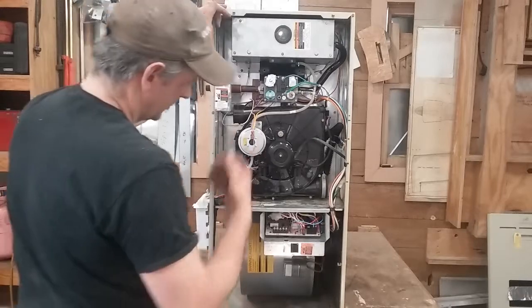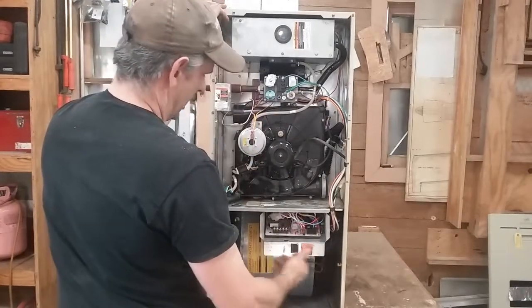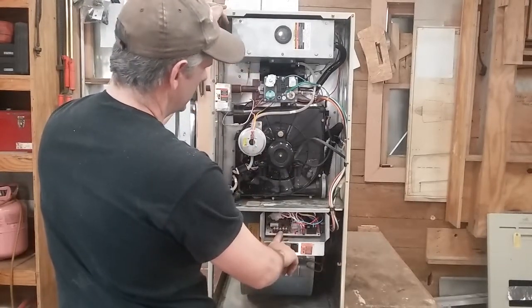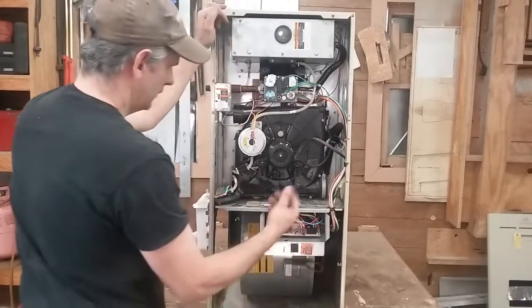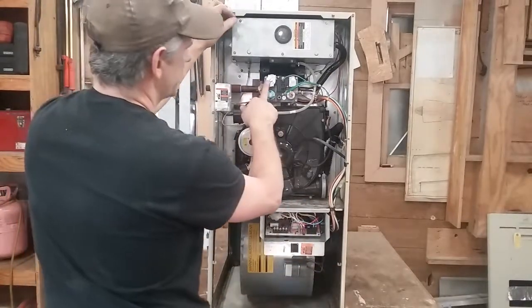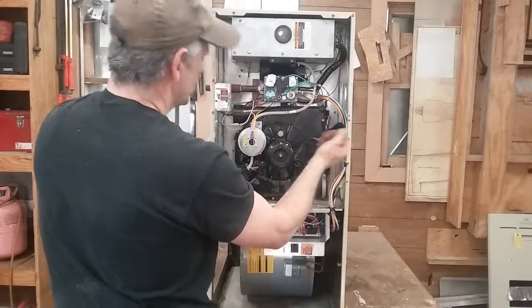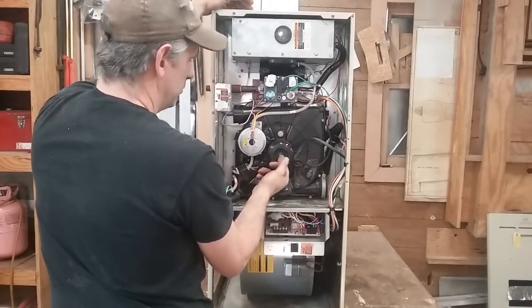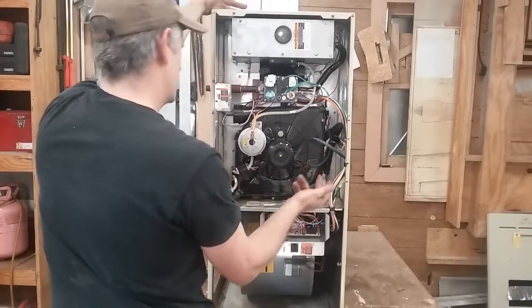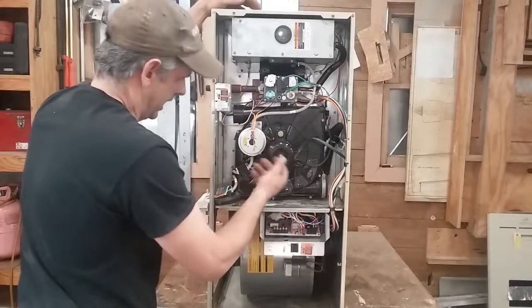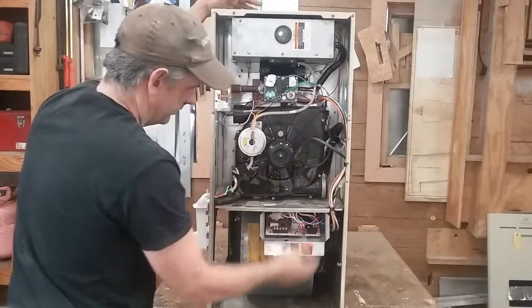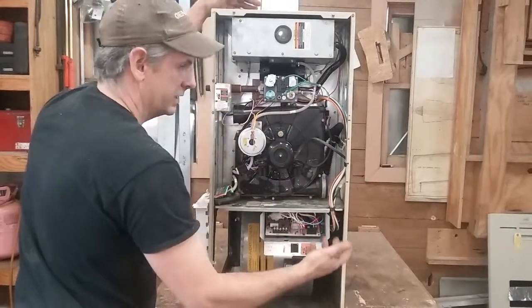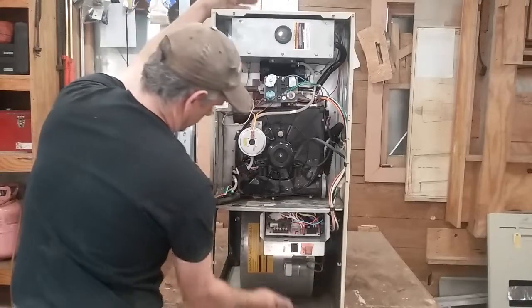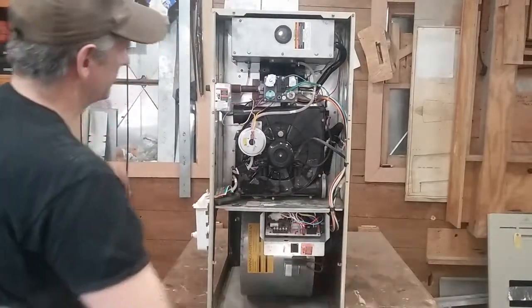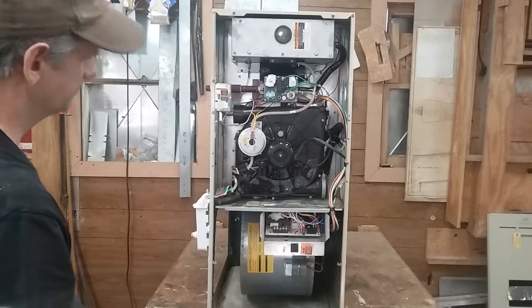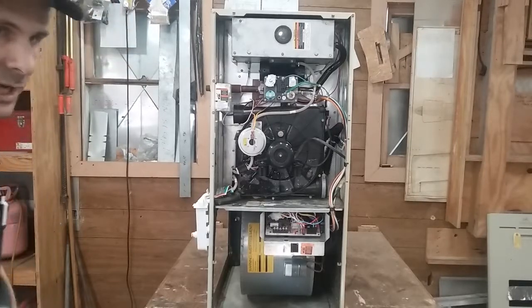Heats the house up. Okay, once the house is warm, W opens back up. First thing that happens is the gas valve shuts off, the flame goes out, and the induced draft blower continues to purge for so many seconds. After it's purged out, it shuts off. Usually about 90 to 180 seconds later, the blower shuts off. Bang, zip. That's about all there is to it. Not a real complicated thing.